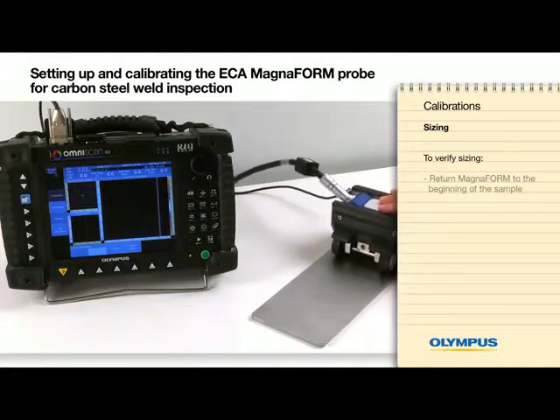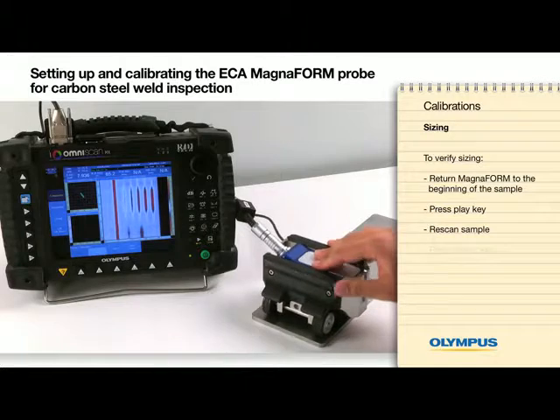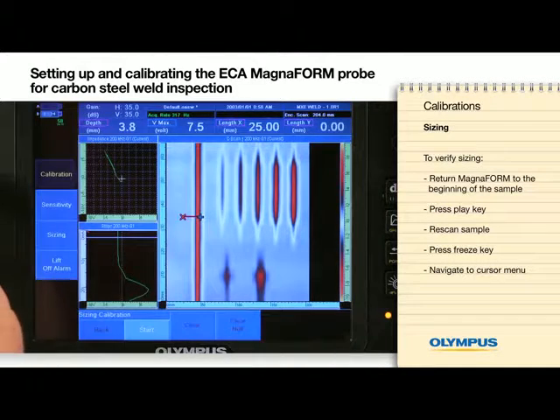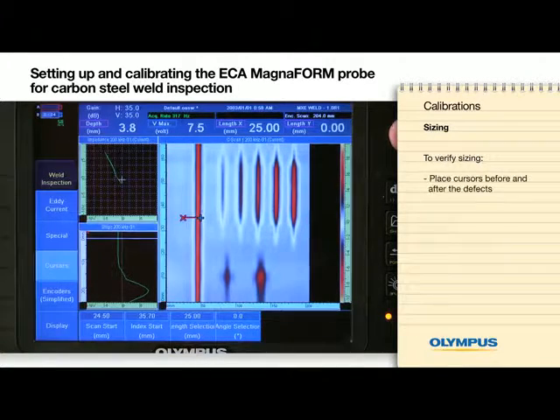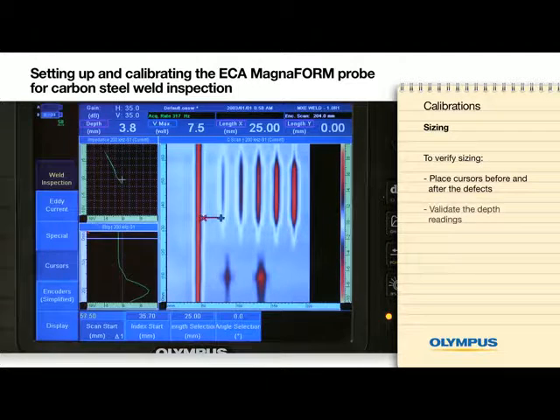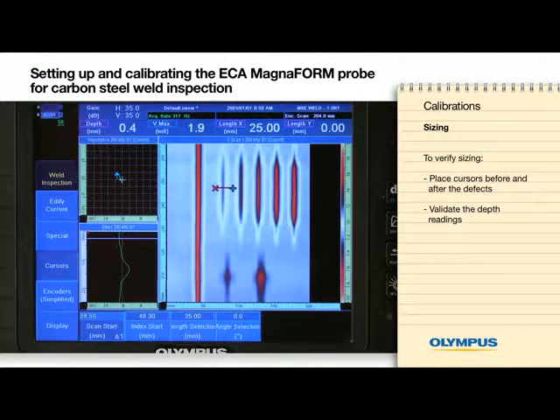To verify the sizing, place the MagnaFORM at the beginning of the sample. Press the play key and re-scan the sample. Press the freeze key and then navigate back to the cursor menu. Place the cursors before and after the defects and validate the depth reading. You have now successfully calibrated your instrument.